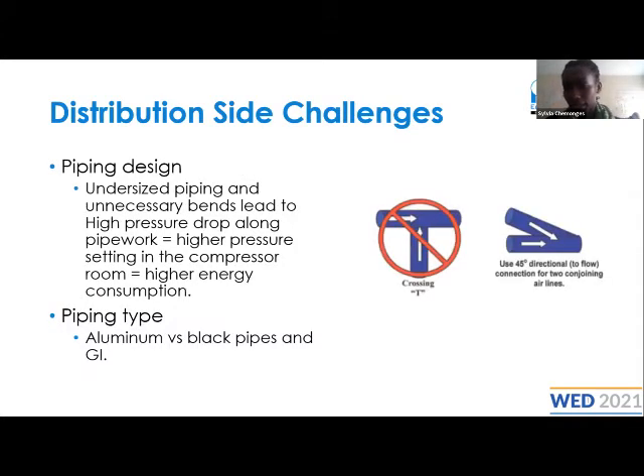Then another challenge on the distribution side is usually the design. You go to site and you see a piping system that has bends everywhere. There's an elbow here, an elbow there, a T-joint here, smaller pipes there. The piping design is usually a big problem. As a result of constricting the flow of compressed air, you end up having high pressure losses within your system. Again, we meet people trying to compensate by increasing the pressure within the system, which you would just fix by using the proper design and the proper pipe size as required.